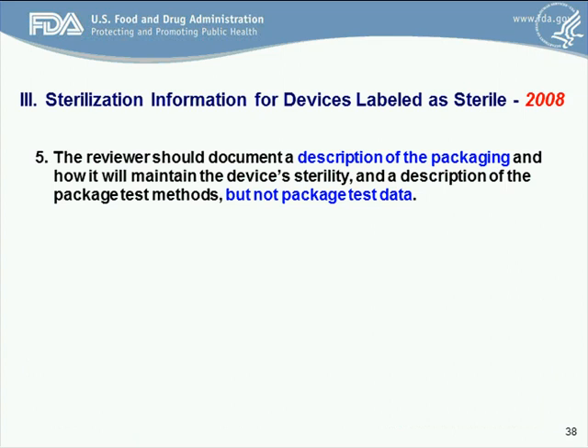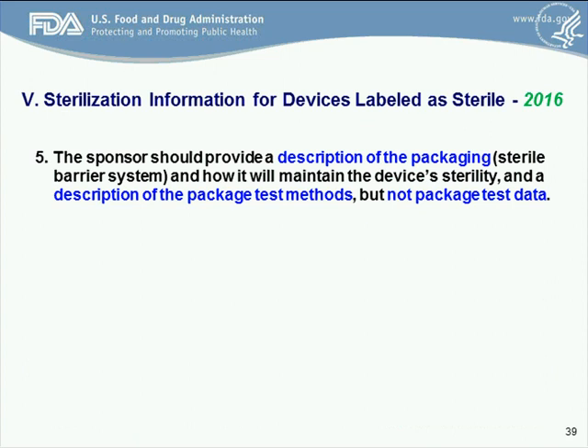The final item — in 2008, we were looking at the description of the packaging designed to maintain the device's sterility, but not the package data itself. When we move ahead to 2016, we're looking at a description of the package designed to maintain sterility, and a description of the package test methods — a summary of exactly what simulations were conducted, what testing was done. For example, what sort of accelerated aging may have been conducted, how that was followed by seal strength testing, what sort of simulated shipping and handling was conducted, and what sort of package integrity testing was done after that. One additional note: for some device types reviewed by some divisions, they do want to see package test data, so check with your relevant division.